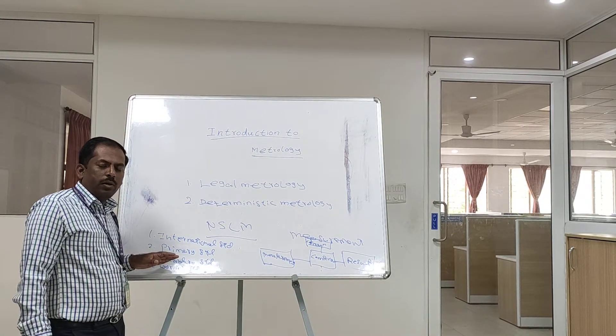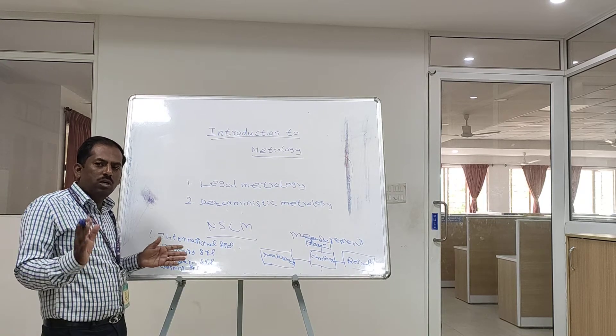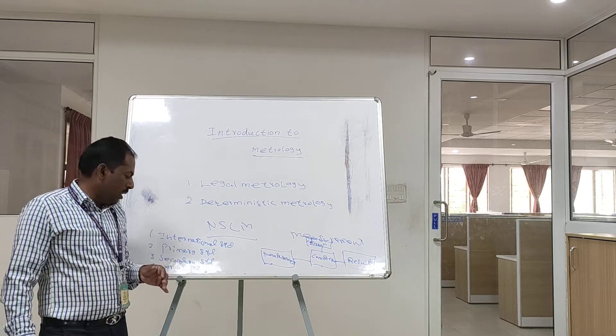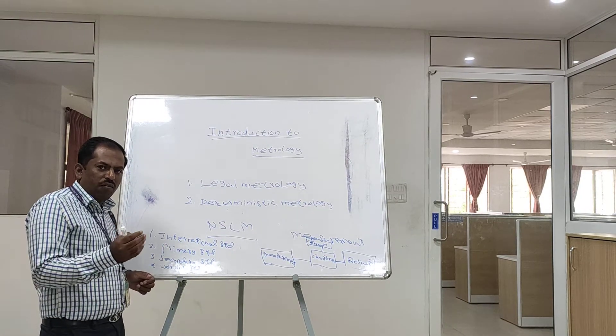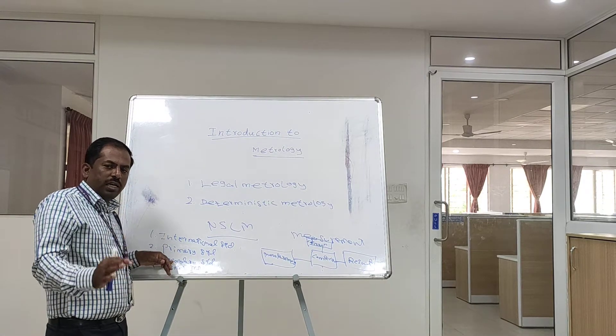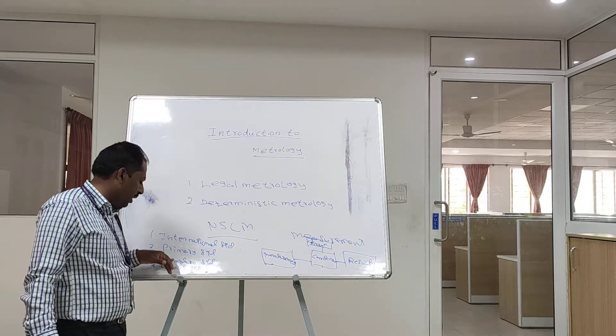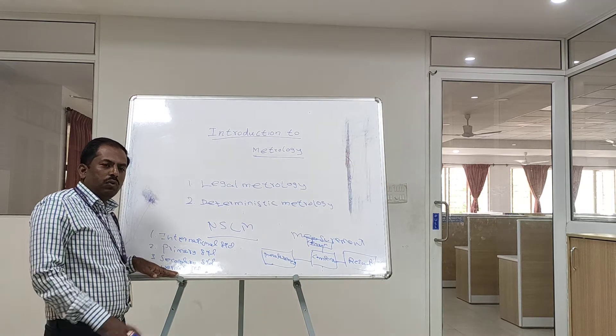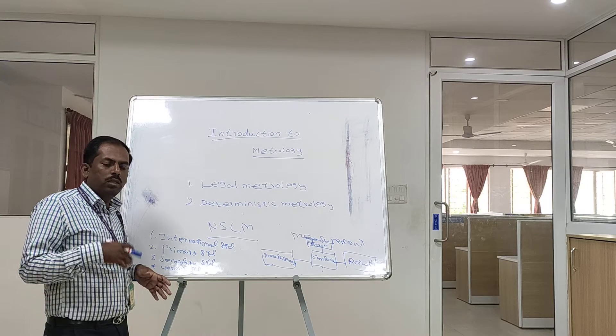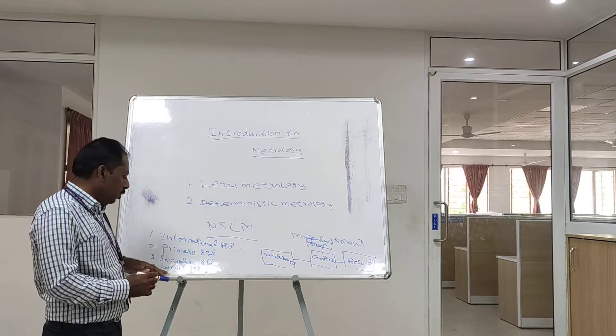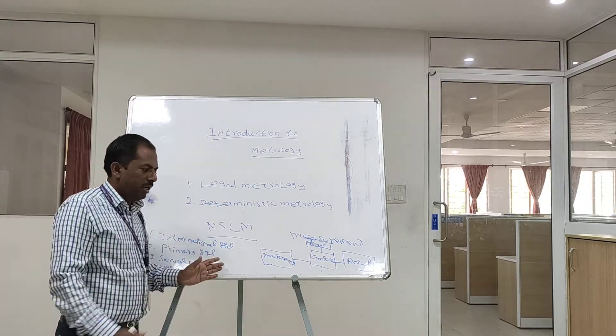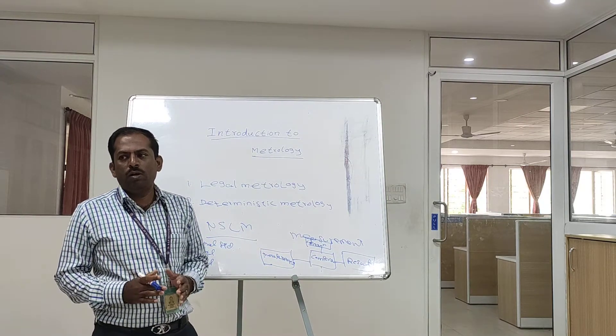The secondary standard is applicable to industries. Every industry will have a laboratory and their own setup, called the tool room lab, where certain instruments are kept for calibration. These secondary standard instruments are calibrated frequently against the primary standards. The working standard is used for inspection on the shop floor, where workers carry out manufacturing and inspection processes. The working standard is calibrated periodically against the secondary standard.